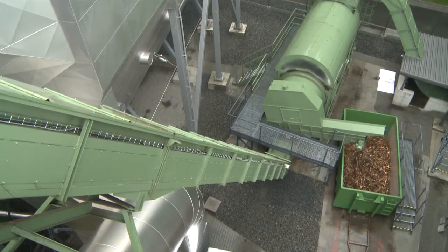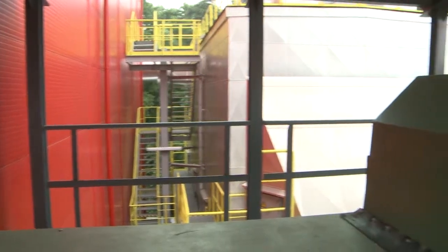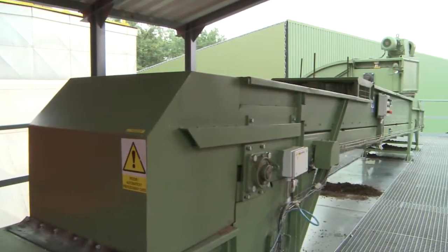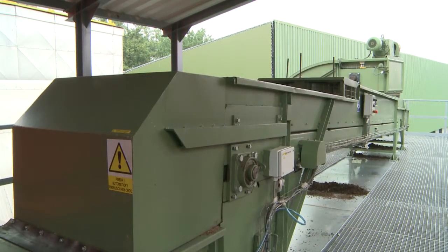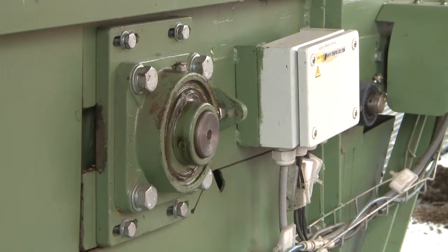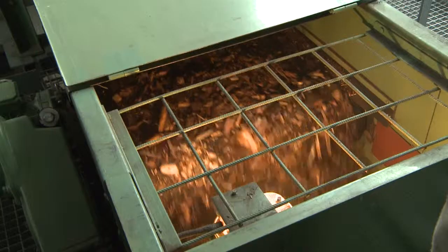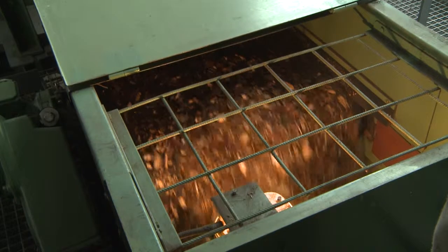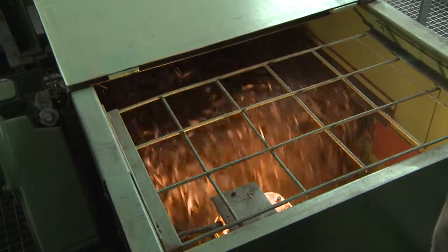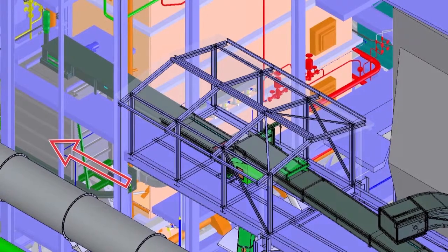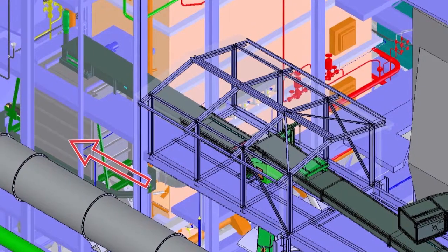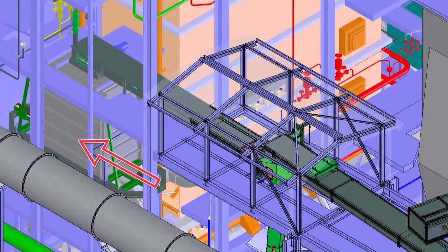The wood chips are delivered by the grab transporter to the upper platform with a conveyor belt. The horizontal conveyor belt is used for the removal of the metals from the wood chips and for its continuous weighing. The equipment for fuel samples extraction is also located here. The wood chips are tipped from the conveyor belt to a tank in front of the boiler, where they are later spread by a hydraulic spreader and transporter to the screw feeders, which move them to the boiler grate.